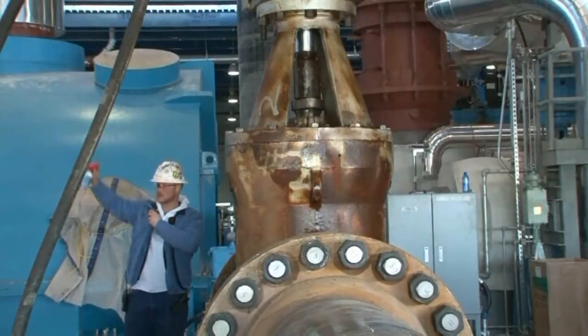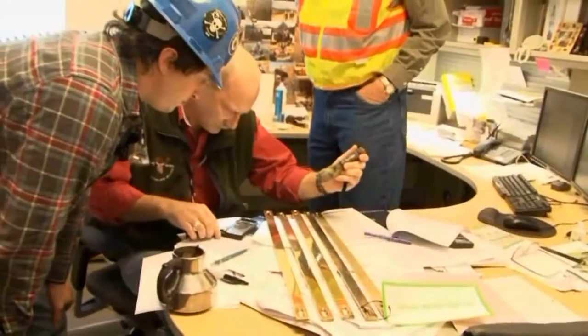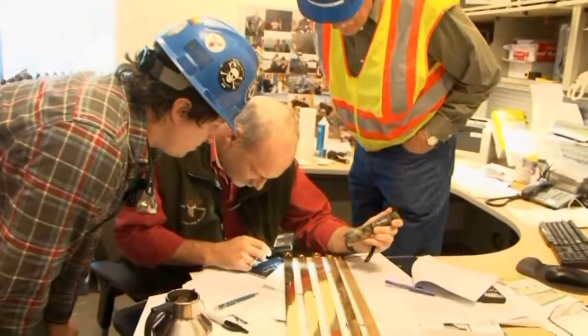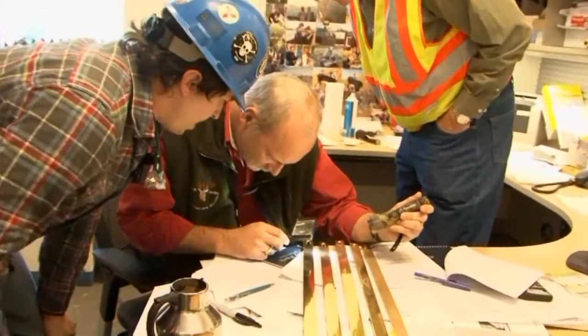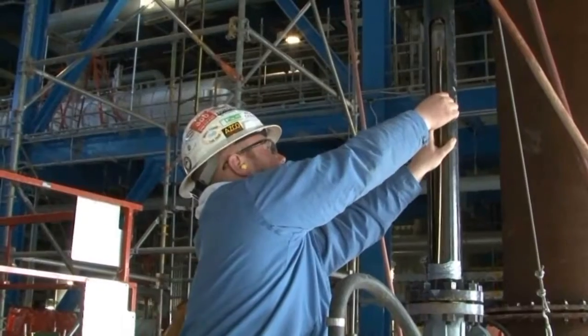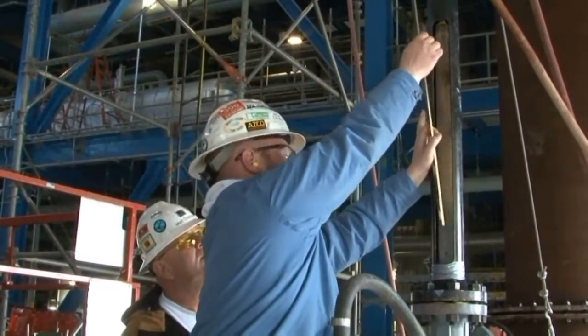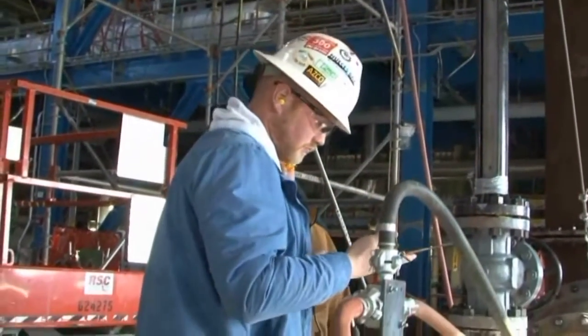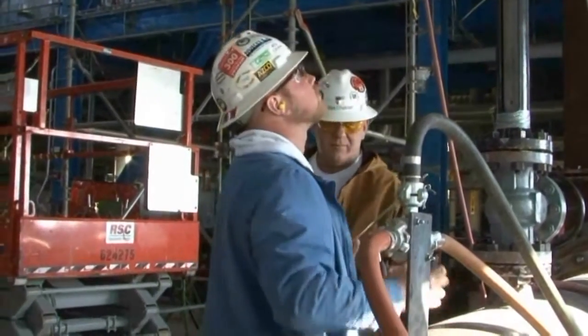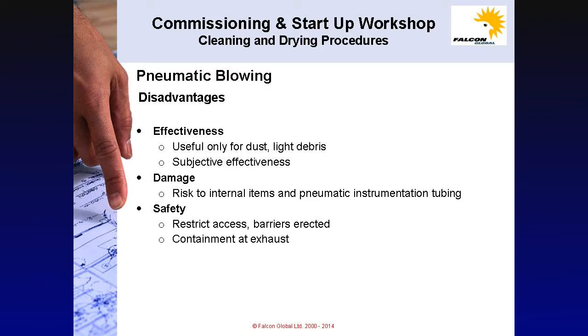Warning sound, major rush of air, checking the results. An important job in Dry Fork Station commissioning. Air blows finished up successfully on January 9th. Because this method was used instead of steam blows, the plant saved several million dollars. The disadvantages are, however, its effectiveness, the risk of damage and safety.